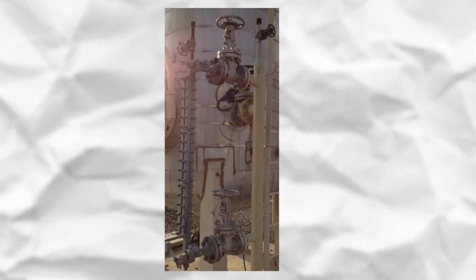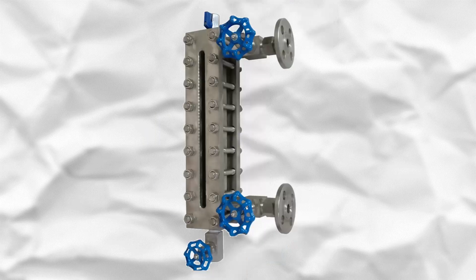The sight glass is connected to the vessel with the help of two piping isolation valves with a size of 2 inches. The flange rating is usually 300 pounds and the flange face is raised face. For this level column, the level gauge, we should install vent and drain valves to make the column empty during maintenance. The size of these valves is usually 3/4 inches or even 1 inch.